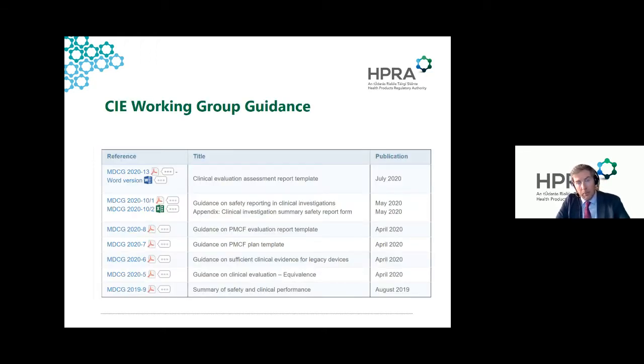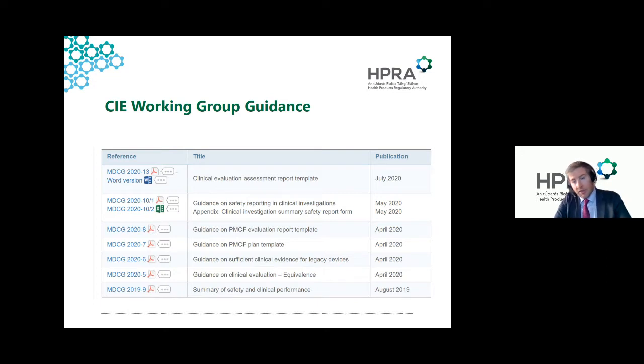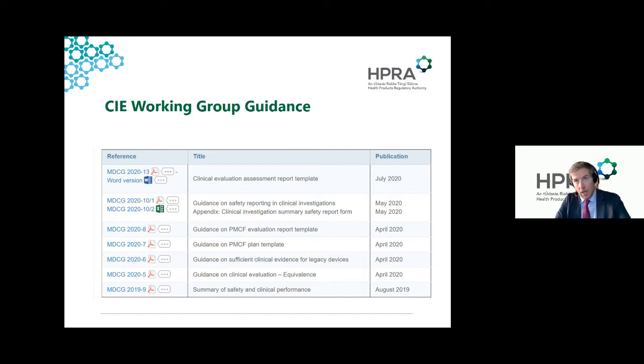There are currently over 70 guidance documents the Commission has been working on for MDR implementation. At the CIE working group we have seven guidance documents published. The first document published was the Summary of Safety and Clinical Performance in August 2019 — a detailed document showing the approach manufacturers should take for completing the SSCP, with a template at the end. The next two documents — MDCG 2020-5 and 2020-6 — we discussed in the last session. The next two documents are standardized templates for post-market planning: a PMCF plan and a PMCF evaluation report.